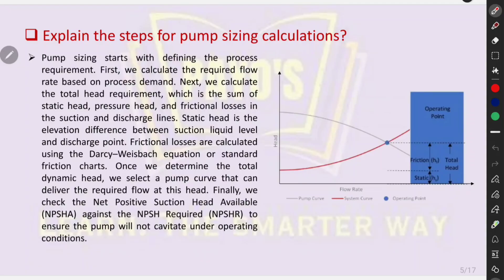Can you explain the steps for pump sizing calculations? Pump sizing starts with defining the process requirement. First, we calculate the required flow rate based on process demand. Next, we calculate the total head requirement, which is the sum of static head, pressure head, and frictional losses in the suction and discharge lines. Static head is the elevation difference between suction liquid level and discharge point. Frictional losses are calculated using the Darcy-Weisbach equation or standard friction charts. Once we determine the total dynamic head, we select a pump curve that can deliver the required flow rate at this head. Finally, we check the net positive suction head available (NPSHA) against NPSH required (NPSHR) to ensure the pump will not cavitate under operating conditions.